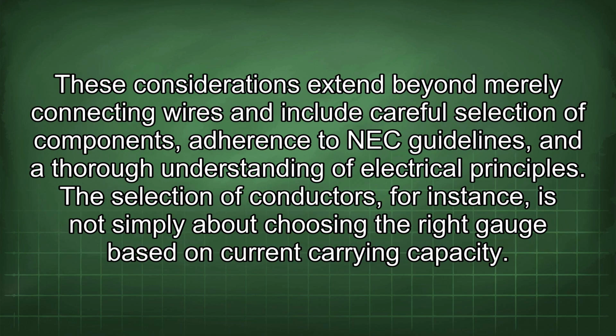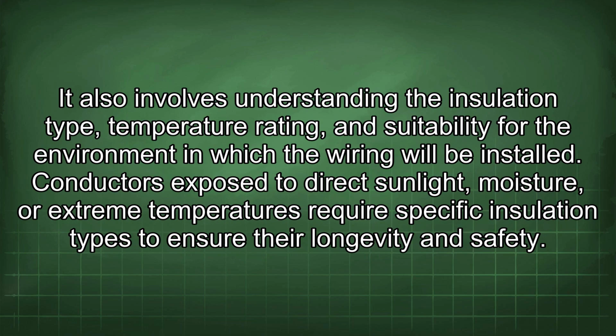These considerations extend beyond merely connecting wires and include careful selection of components, adherence to NEC guidelines, and a thorough understanding of electrical principles. The selection of conductors, for instance, is not simply about choosing the right gauge based on current carrying capacity. It also involves understanding the insulation type, temperature rating, and suitability for the environment in which the wiring will be installed. Conductors exposed to direct sunlight, moisture, or extreme temperatures require specific insulation types to ensure their longevity and safety.